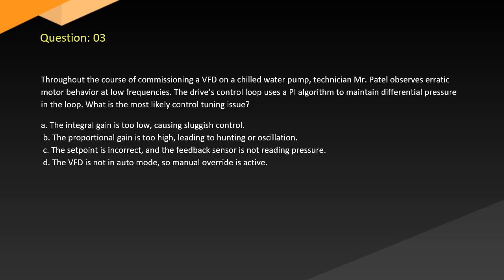A. The integral gain is too low, causing sluggish control. B. The proportional gain is too high, leading to hunting or oscillation. C. The set point is incorrect and the feedback sensor is not reading pressure. D. The VFD is not in auto mode, so manual override is active.